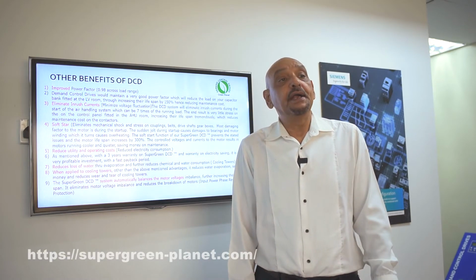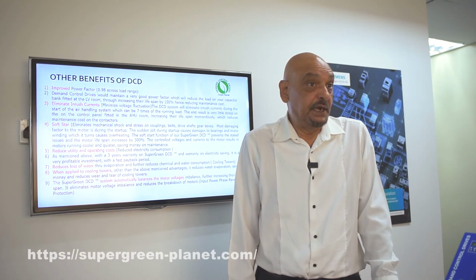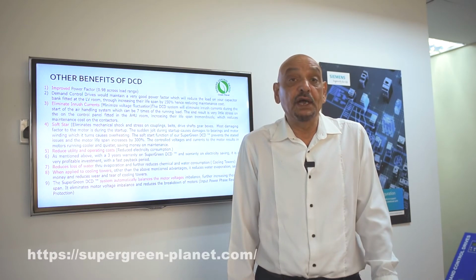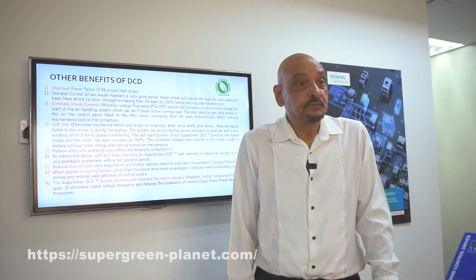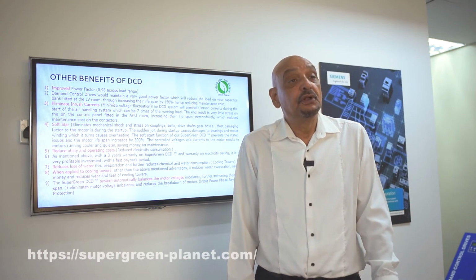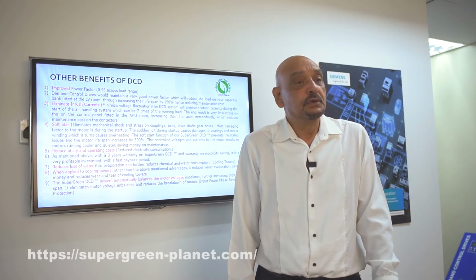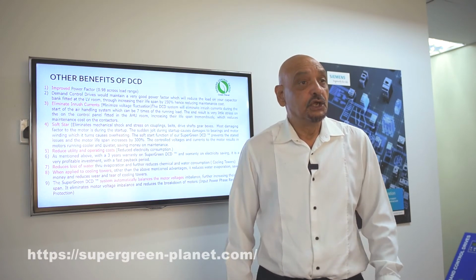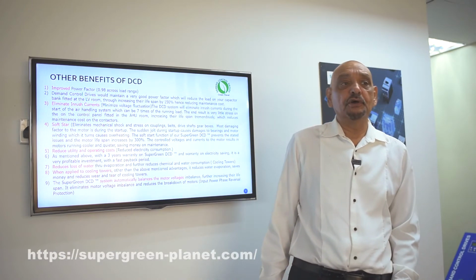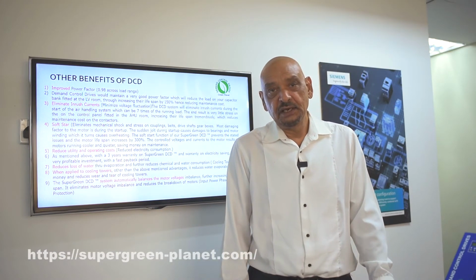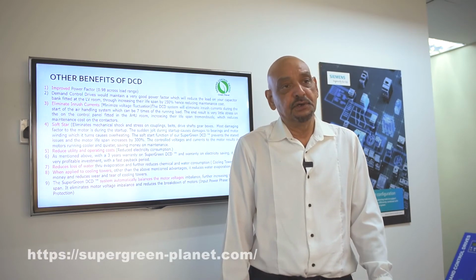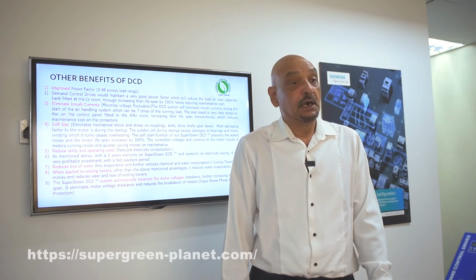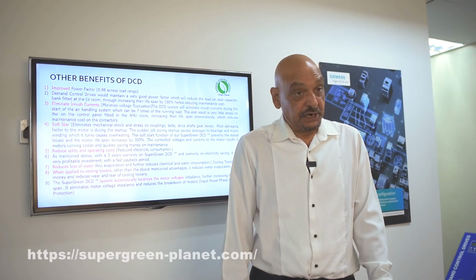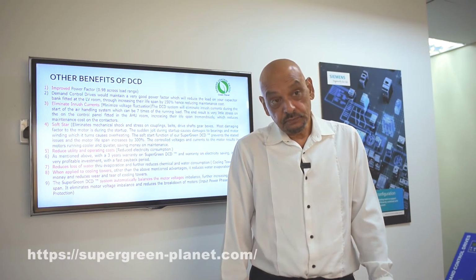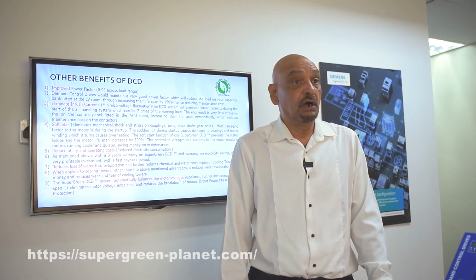Now, why does this make a difference? You may ask a question like, so what? I have got a cap bank. Now, if at the equipment level your power factor is improved to 0.98, you will have less stress on your capacitor banks, which means that as far as your capacitor banks are concerned, they are going to give you a much longer lifespan. Yet again, this is reducing your maintenance cost.